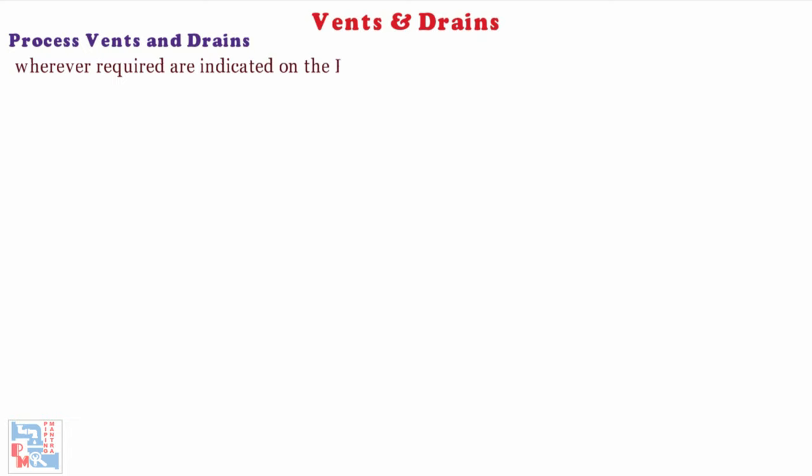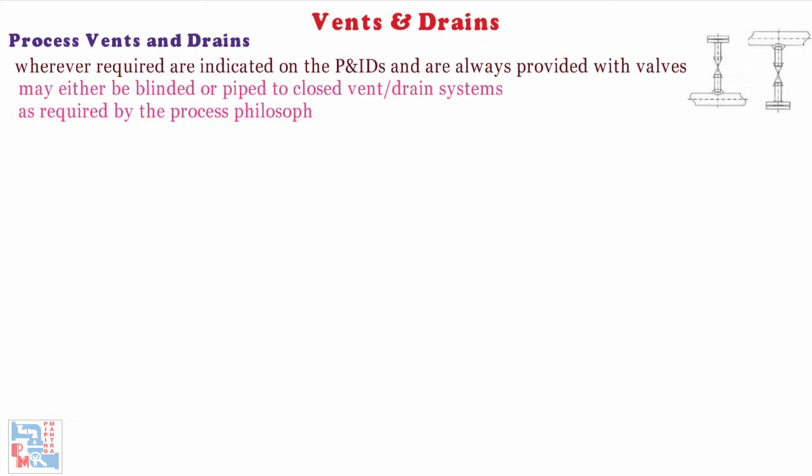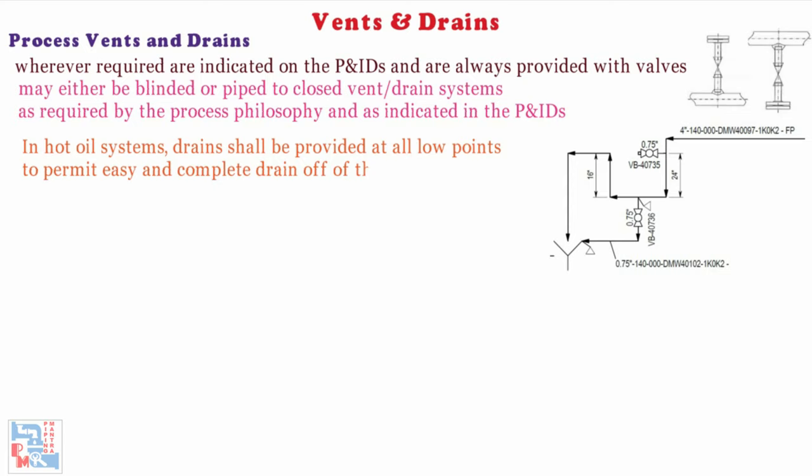Now comes the process vents and drains. Process vents and drains, wherever required, are indicated on the P&IDs and are always provided with valves. Process vents and drains may either be blinded or piped to closed vent/drain systems as required by the process and as indicated in the P&IDs. In hot oil systems, drains shall be provided at all low points to permit easy and complete drain-off of the system.